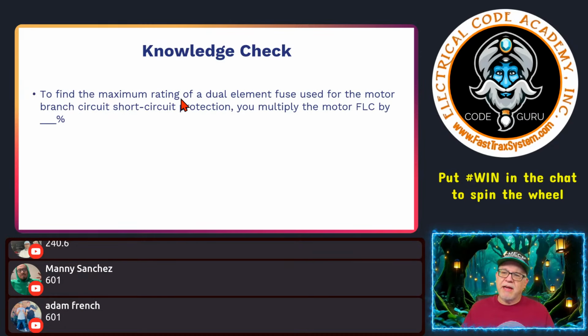To find the maximum rating of a dual element fuse used for the motor branch circuit, short circuit, ground fault protection. You multiply the motor's FLC by what percentage? So if we're sizing a motor and we're using dual element fuses, what table do we go to? And what is the percentage that we're going to use? It's a percentage of the FLC, okay, using the FLC of that motor, which is in what? 430.248, 249, or 250, those type of things.